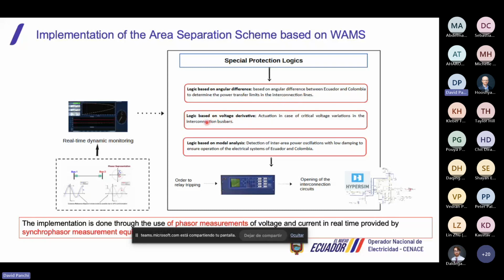The other logic is based on voltage derivatives, in case of critical voltage variations in the interconnection busbar. And the last logic is based on modal analysis. With the phasor data, we do the modal analysis in the Hypersim software. So we detect the inter-area power oscillation with low damping and send the trip to ensure the electrical system of Ecuador and Colombia operates well.